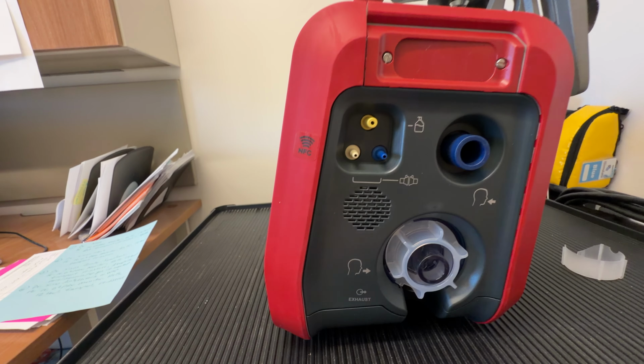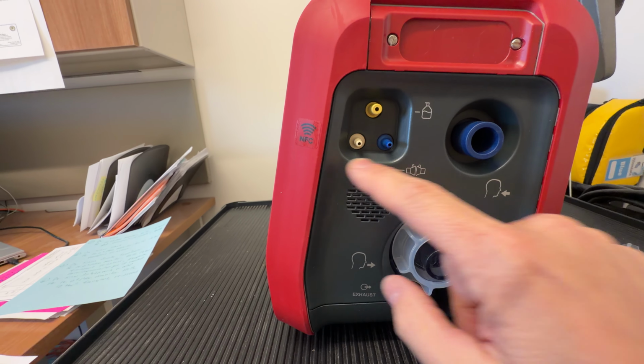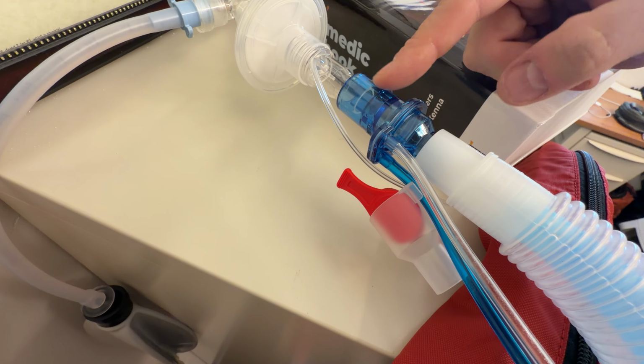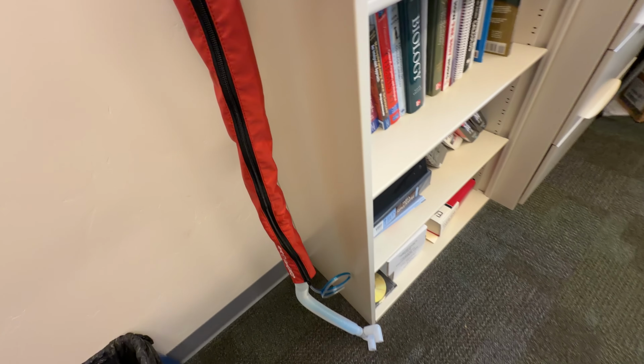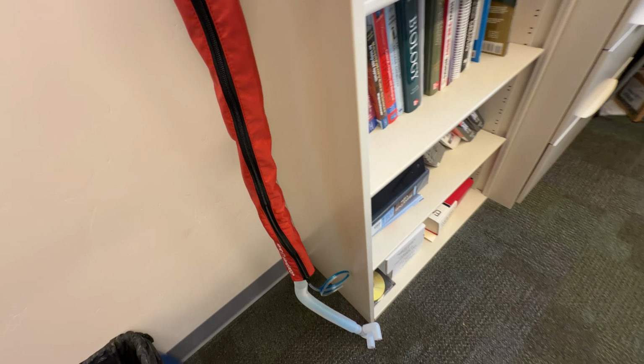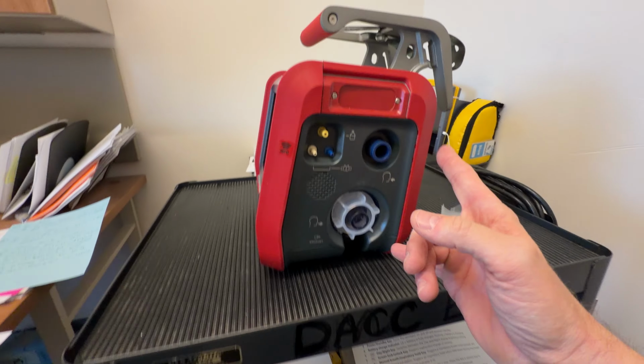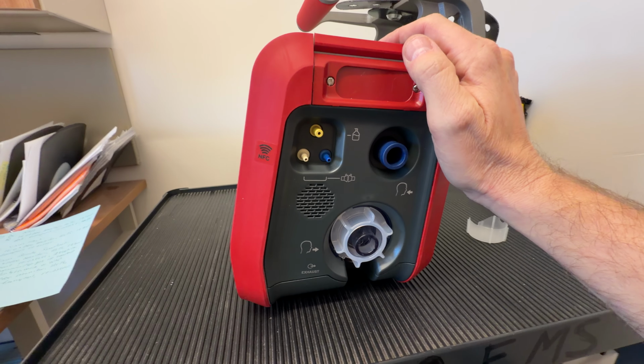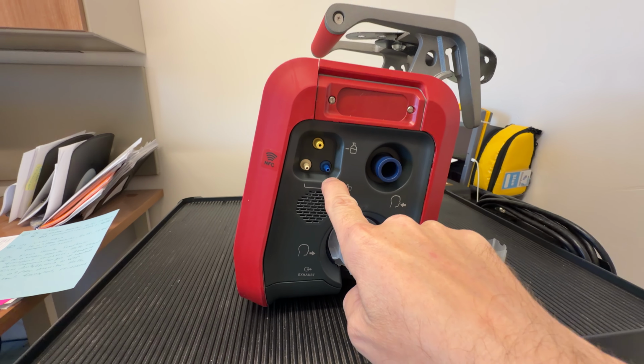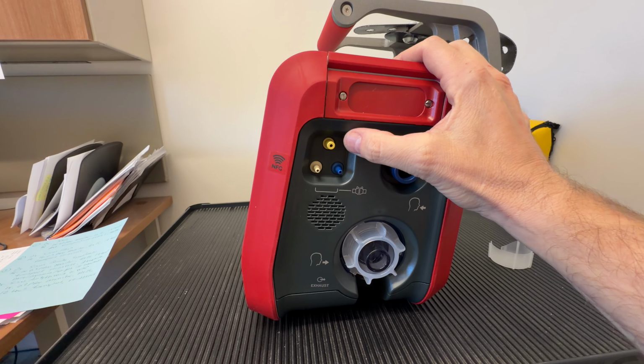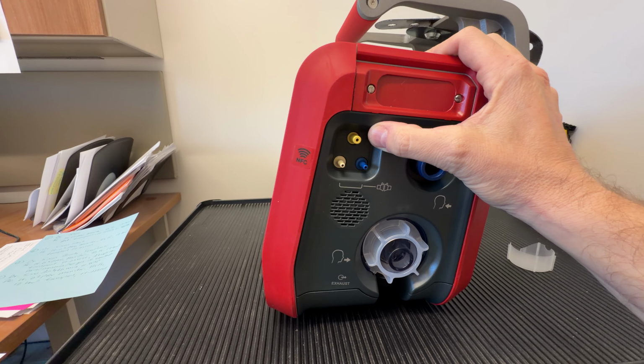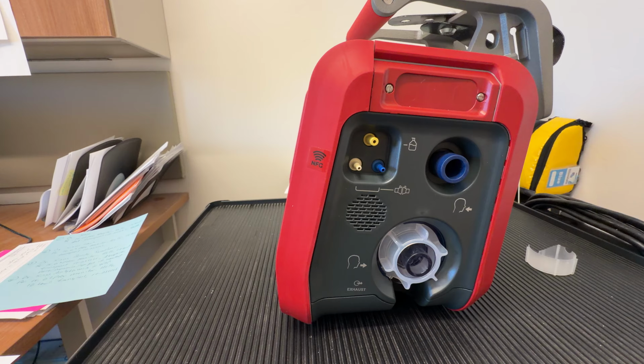All right, this is where your flow sensor tubing attaches. So if you remember from the prior video, we talked about the inspiratory and expiratory flow sensor and the tubing, white color and blue color for inspiratory and expiratory sensing. So these tubes right here are going to attach to the ventilator. And the cool thing about this is you can see the way that this is set up on the coaxial tubing. There's only one way it can connect to the ventilator, and I'll show you how to connect that here in a little bit. But the blue flow sensor tubing goes here, white goes here, and then this right here is where your nebulizer tubing would go, and it would attach to your nebulizer, and then you'd have your nebulizer in line in your ventilator circuit.